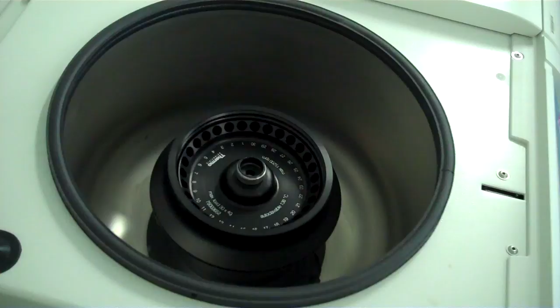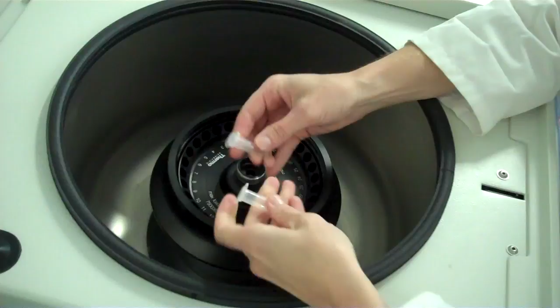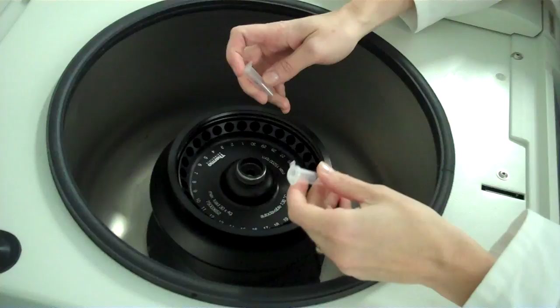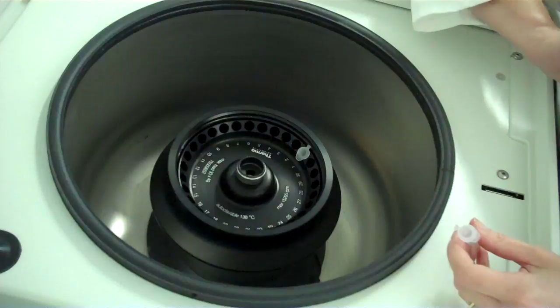Now, during the molecular biology portion of the laboratory, you will be using this microcentrifuge tube rotor. The one that we use has 30 places to hold microcentrifuge tubes. And it's actually easy to create an unbalanced rotor if you're not paying attention. So the easiest way to do this is to put your microcentrifuge tube into one of the positions and read what the number is. In this case, the number is 1. Simply add 15 to that, and that will tell you which position the tube should be on the other side. Note that I'm putting the hinges facing out when I place these into the rotor.